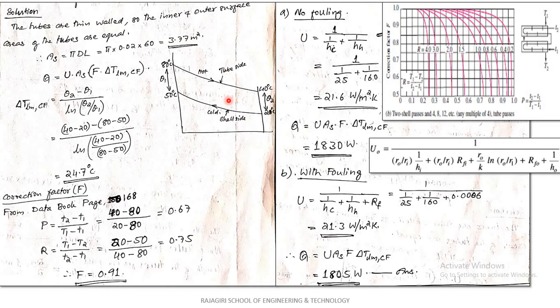For a multi-pass heat exchanger, calculate a correction factor F from the data book page 168 using the chart for two shell-pass, four (or multiple of four) tube-pass arrangements. This correction factor F, multiplied with the LMTD for a counter flow heat exchanger, gives the LMTD of the multi-pass heat exchanger. The heat transfer rate is then q = U·A·F·ΔT_lm,CF.